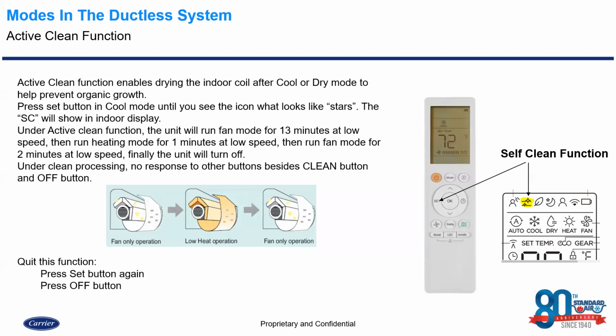Okay, so when you are in this active clean or self-clean function, the unit's going to run its fan mode after it comes out of call for cooling for 13 minutes at low speed. Then it's going to energize that reversing valve and then run the system in heating mode, sending hot gas to dry out that indoor coil for 1 minute at a low fan speed. Then it will de-energize the reversing valve and then only run that fan for 2 minutes at low speed. Finally, that unit will turn off and come out of this mode.